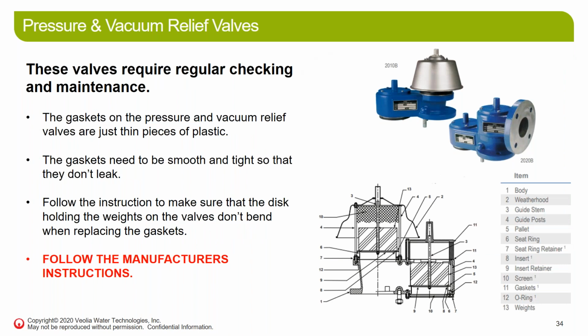Regular maintenance: typically most plants have at least a yearly requirement to maintain these vessels, but I think the OEMs usually recommend even more frequent maintenance. There are gaskets on these pressure and vacuum relief valves that are just thin pieces of plastic. Those can wear over time. They can be damaged if the valve opens and shuts, so you could get leaking if the valve lifts and closes. You've got to be careful. One, they're delicate. Two, if you're replacing the weights or the gaskets, when you take the weights on and off, make sure you don't bend the gaskets or damage them. Most of the valves that we supply are Varec biogas valves, so make sure you look at their instructions and follow them.